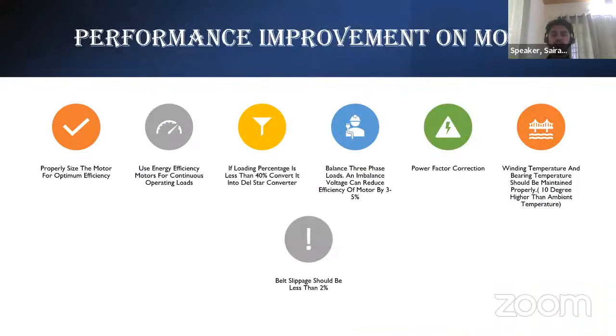Performance improvement on motors: for getting better efficiency, we have to do proper sizing of the motor. Then energy efficient motors have to be installed, like IE4 or IE3 motors. If the loading percentage is lower than 40%, then you can opt for a star delta star converter. Then all three phases have to be balanced, the supply has to be balanced, and the power factor has to be maintained in the circuit so that there won't be any losses. Then winding temperature and bearing temperature should be properly maintained.